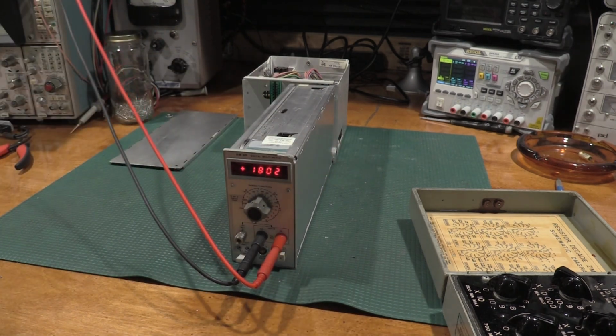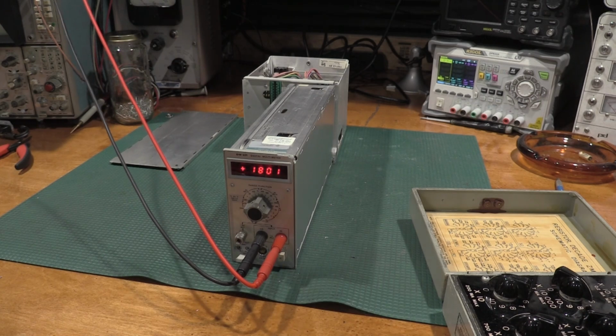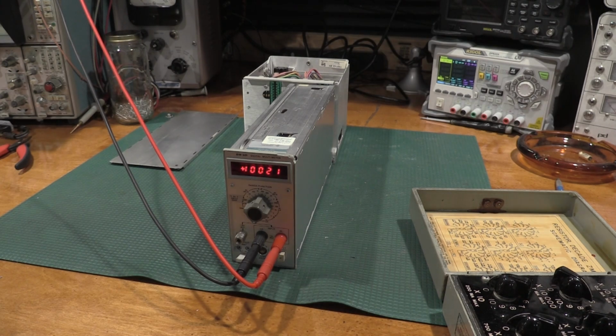Here's the 2 amp range. I think my SMU maxes out at 2 amps, or at an amp, but let's try 2 amps and see if it'll give it to me. No, 1 amp, so we'll check it at 1. I need the high current SMU to 1 amp. And we're good at 1 amp with a half a volt burden voltage. So amp range looks good.